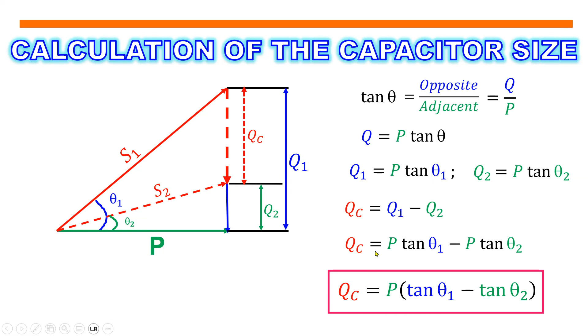So yung QC, para makuha natin yung length na to, that is equals to yung buong Q1, iminus natin yung Q sub 2. So QC is equals to Q sub 1 minus Q sub 2. Then substitute yung mga values ng ating Q1 and Q sub 2, that is equals to Q sub C is equals to P tangent theta 1 minus P tangent theta 2. Then ipa-factor out natin yung P. So Q sub C is equals to P multiplied by tangent theta 1, yung malaking theta, minus tangent theta 2, yung kulay green. So that will be the equation na gagamitin natin para makompute yung capacitor bank size.